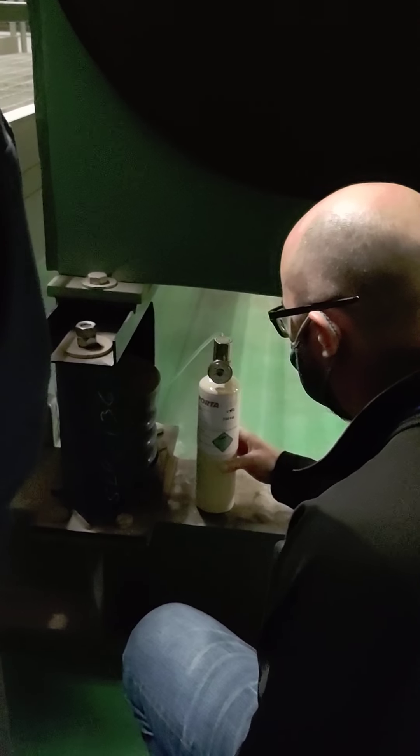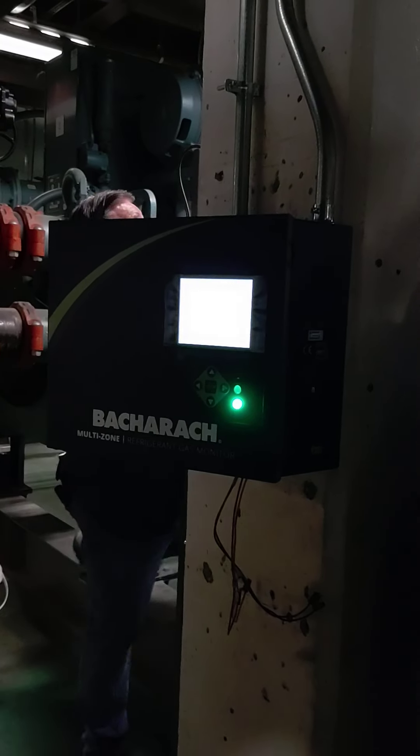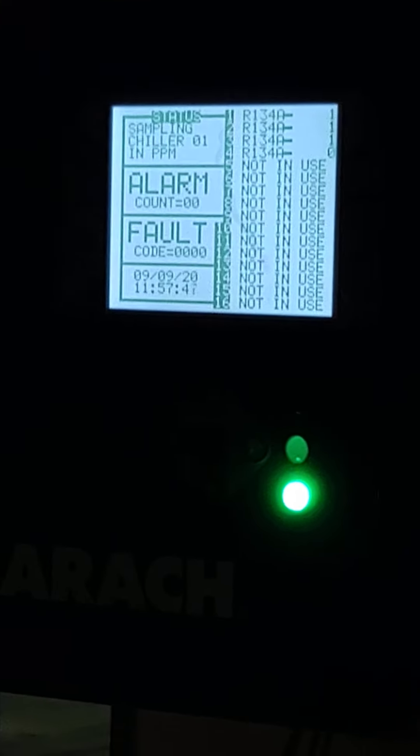That's just a test bottle. Is that actual refrigerant or what is that? It's tetrafluoroethane and air. I'm not positive that's actually the refrigerant, but that's probably what's inside of it. I doubt that it's actually refrigerant. I'll just plug this in — it's got 200 psi on it. We're actually on chiller one right now, so we may or may not see the alarm initially.